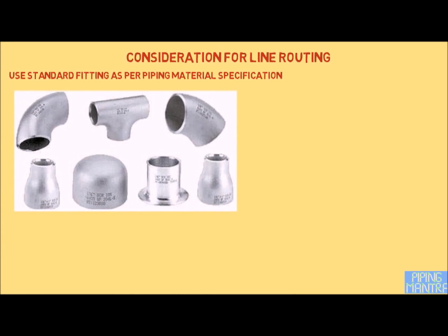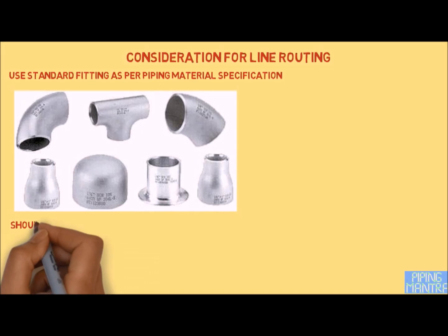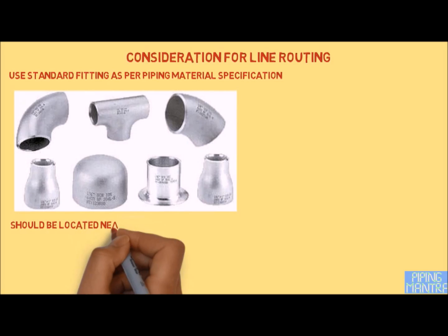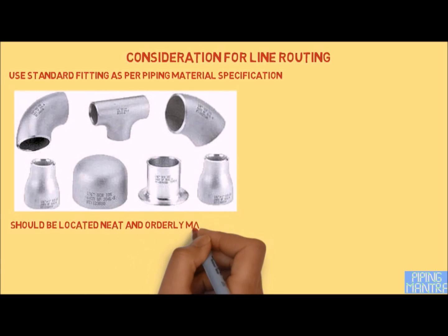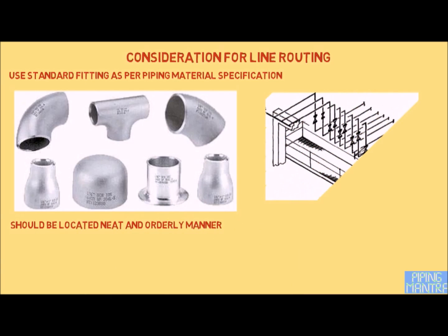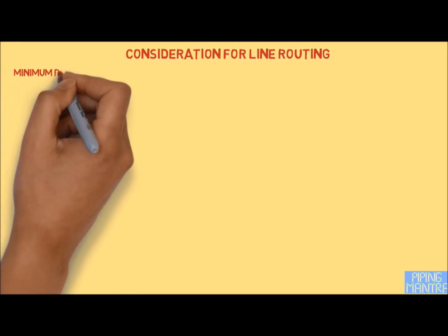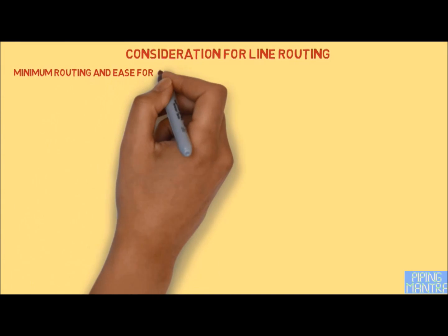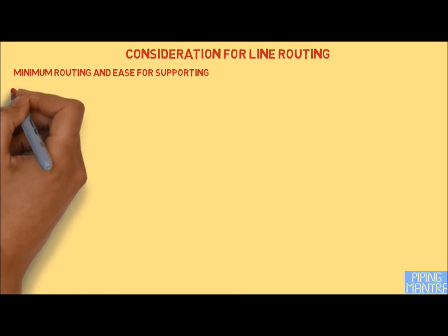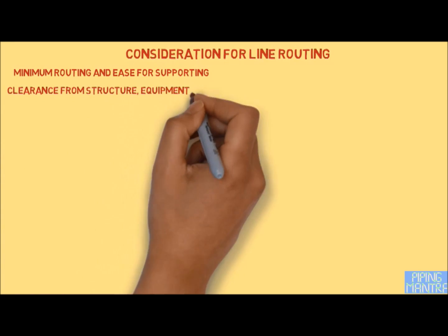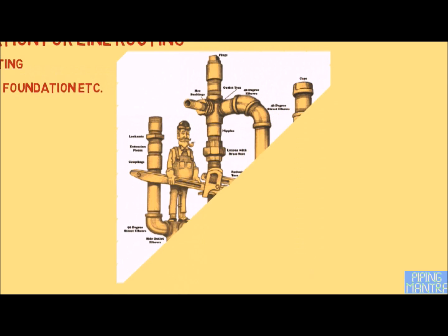Piping should be located in a neat and orderly manner. Spacing between pipes should be checked properly, considering staggered flange orientation or as per client requirement. We should also consider proper insulation thickness and thermal movement. Piping should be as short as possible, with ease of supporting. We need to provide at least 50 mm to 200 mm clearance from structures, equipment, or foundations for wrench access and other requirements.